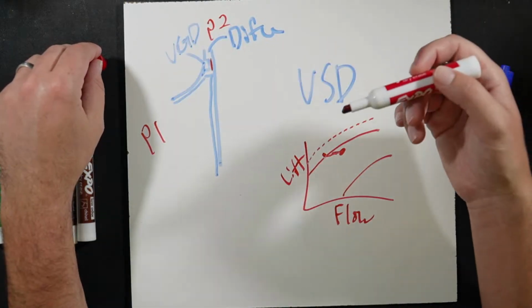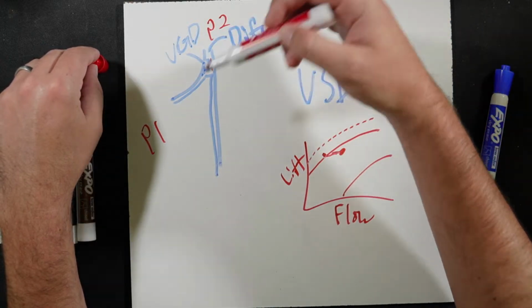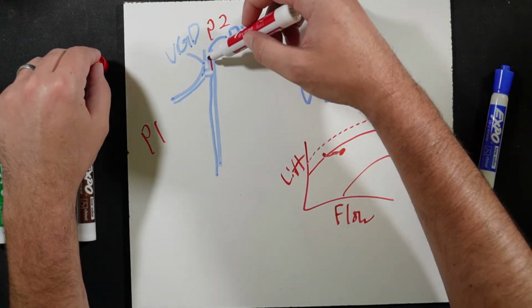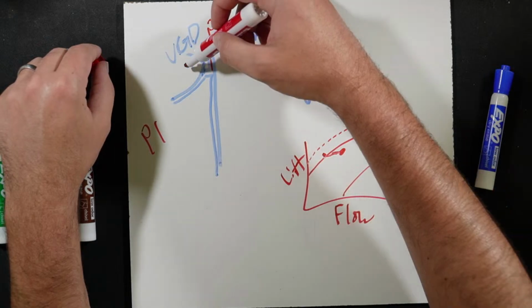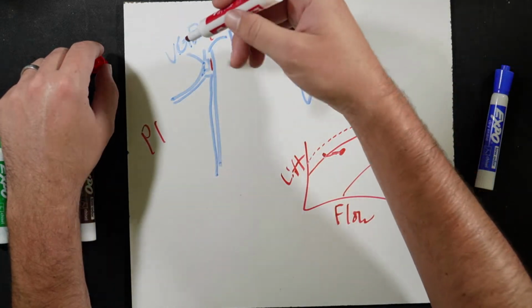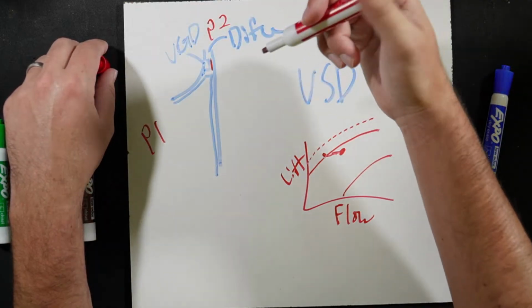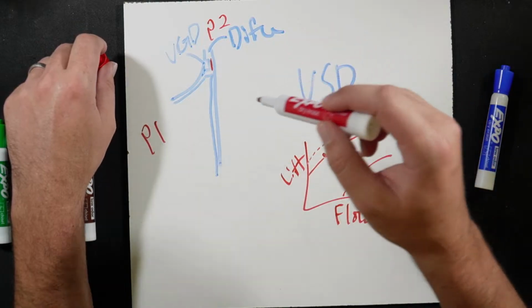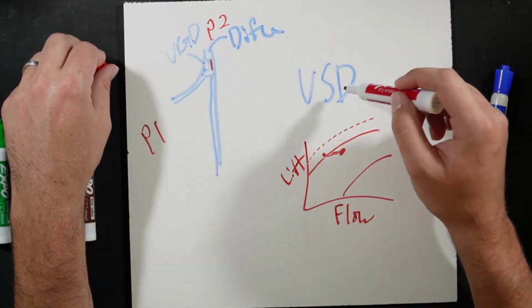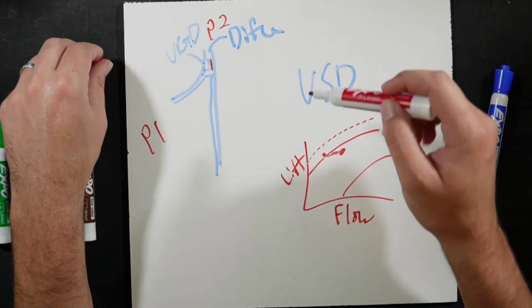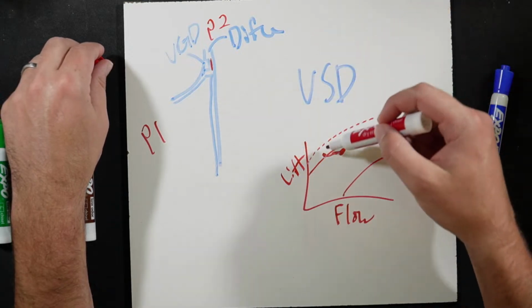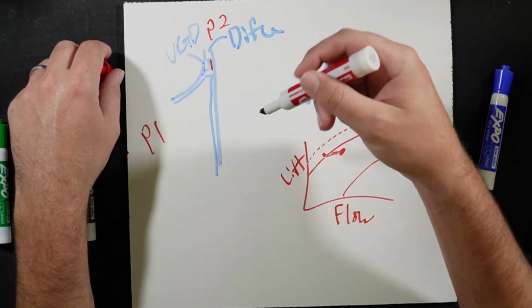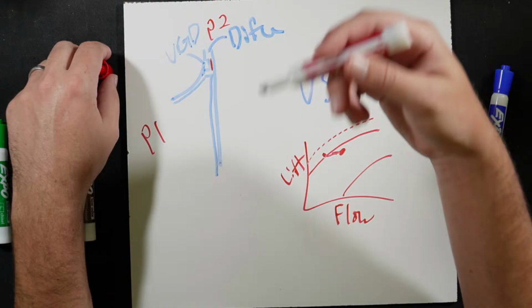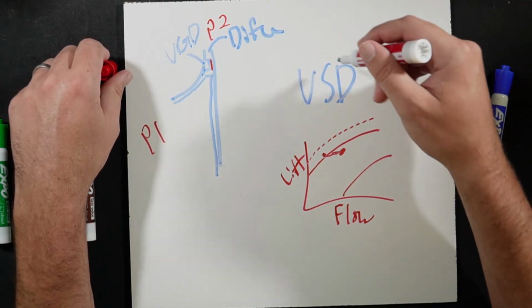Once the chiller is ready to load up, this is just your sequence of operation. Once we're loading up, then the VGD will open. It will go as open as it can, and if that means it's able to go to completely open, then that's awesome. Then, once this is fully open, our VSD will begin to increase speed, which increases our flow. This whole process is the staging up sequence. So we will stage up as far as we need to.